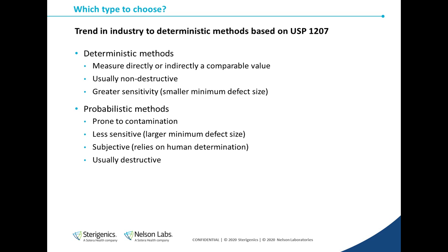In contrast, the probabilistic methods are subjective. You're relying on a human to make a judgment call versus a machine to measure a value. Probabilistic methods are more prone to contamination because the container usually needs to be opened in some way during the test, and this is what makes those methods destructive. Finally, as discussed earlier, the minimum defect size is usually larger with probabilistic methods.